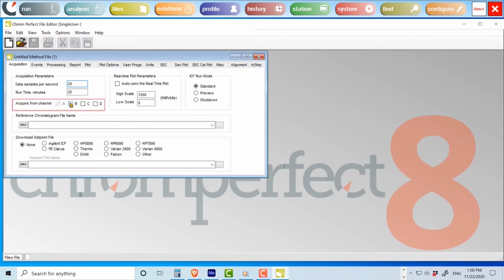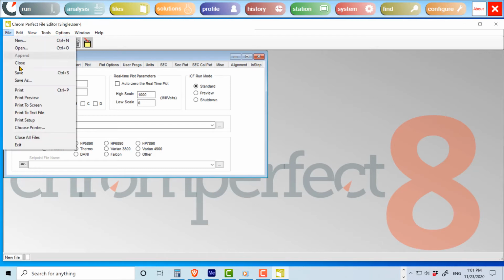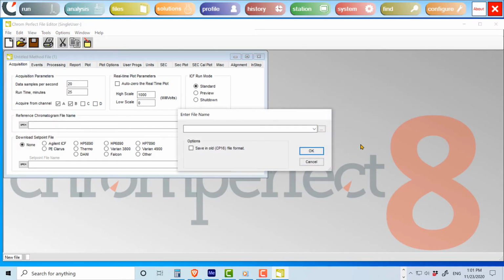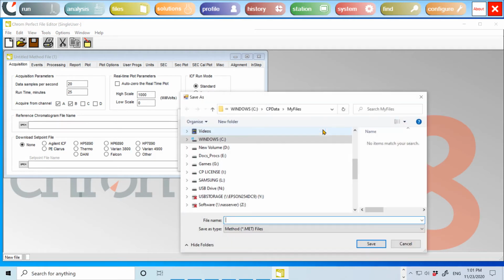The Acquire From channel setting does not matter if the instrument has only one configured detector. In a multi-detector instrument, these settings determine which of the configured channels is active as far as acquisition is concerned. We wish to acquire data from all channels, so check as many boxes as there are channels. The other fields on the Acquisition tab need no attention currently. When you have finished editing, pull down the File menu and choose Save. When the dialog appears, give the new method file an appropriate name and save it in one of your new directories.